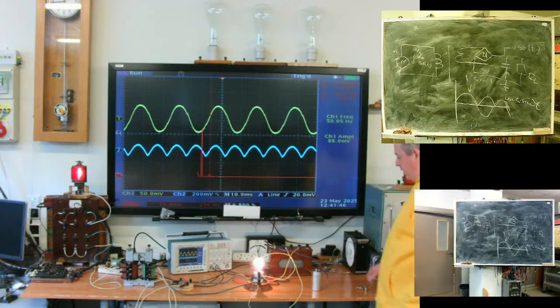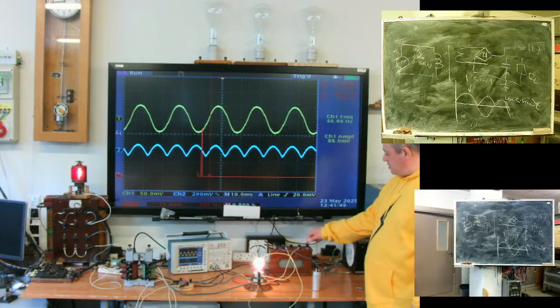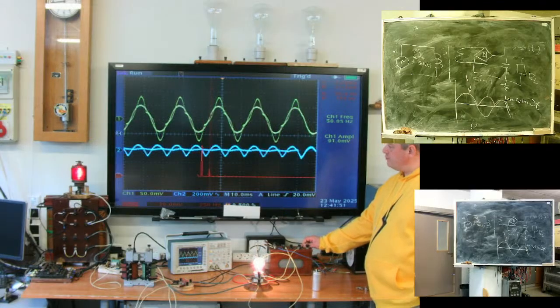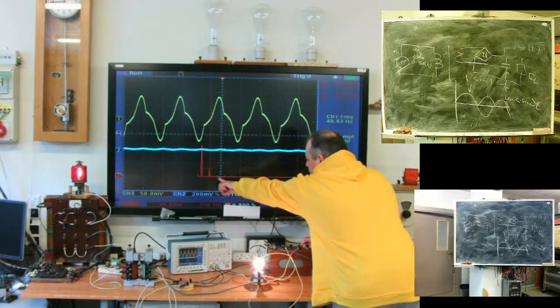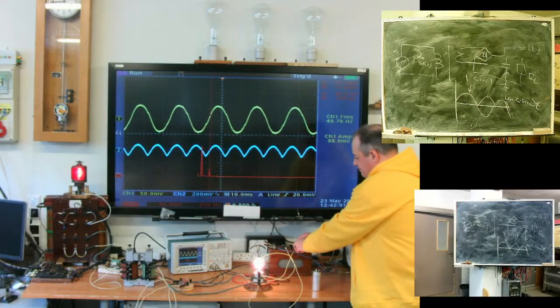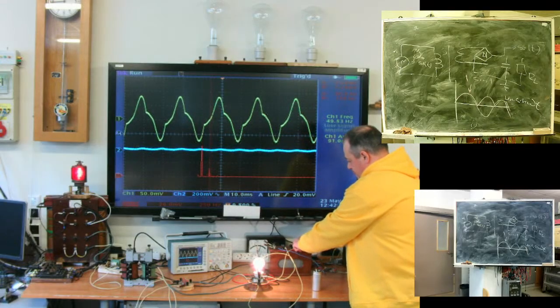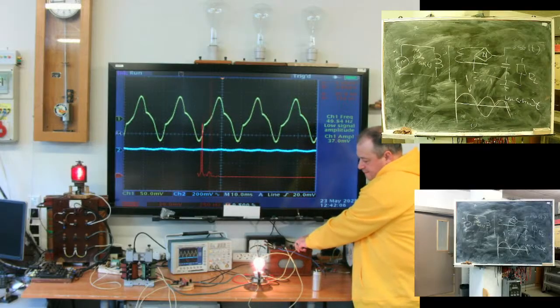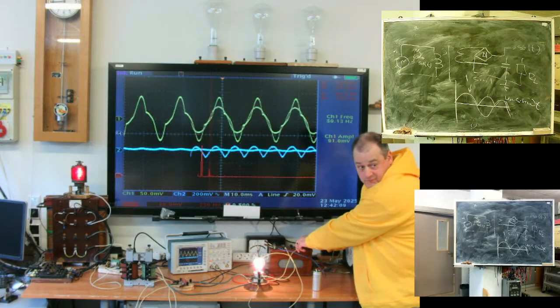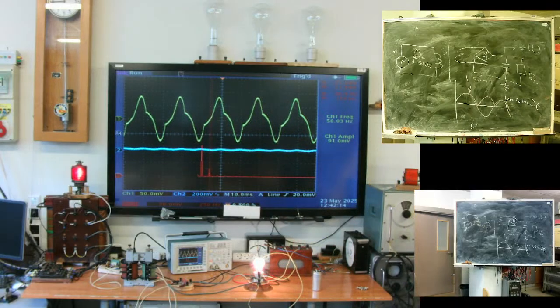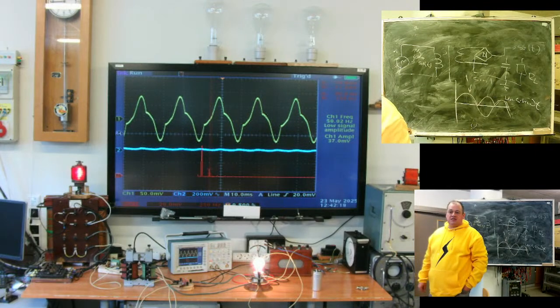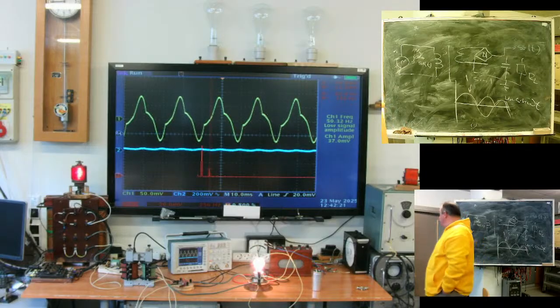Red line, spectrum of primary current. Addition of filter. See what happens? Distortion and observable third, fifth, seventh harmonic. Why does the addition of a filter cause distortion in the primary current? The idea is simple.